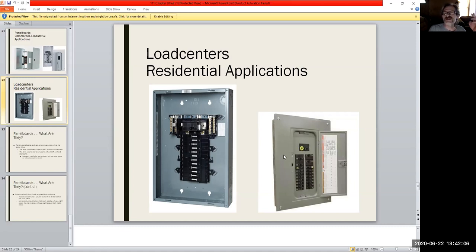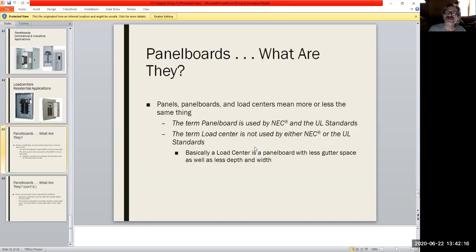And it's very common. This is very typical of what they look like. The sizes can change, depending on how large you want this to be, how many branches you think you're going to have to feed, that kind of thing. But panels, panel boards, load centers, they're pretty much all the same type of thing. They get fed a main line from somewhere, and it's going to have a main disconnect to it.